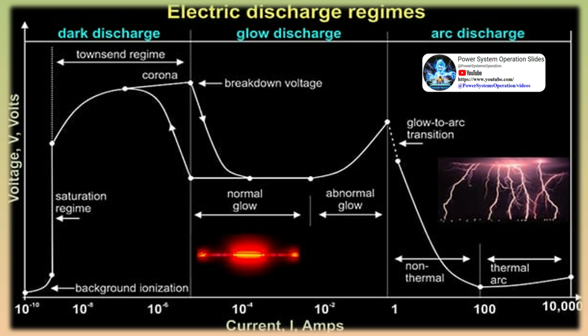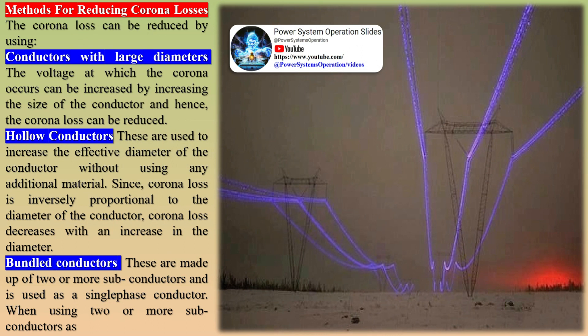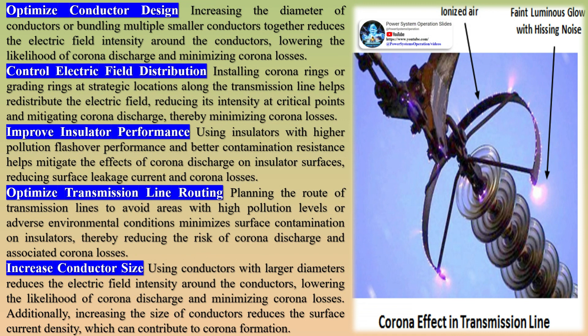Spacing between conductors: design engineers calculate the spacing between the two conductors in the transmission line after careful and extensive research, as corona discharge is affected by conductor spacing. If the distance between two conductors is very large compared to the diameter of the conductor, the corona effect may not occur, because larger distance between conductors reduces the electrostatic stress at the conductor surface, thus avoiding corona formation. Atmosphere: since corona is formed due to ionization of air surrounding the conductors, it is affected by the physical state of the atmosphere. In stormy weather, the number of ions is more than in normal weather, and the increase in ions decreases the breakdown voltage, so corona occurs at much less voltage compared to fair weather.